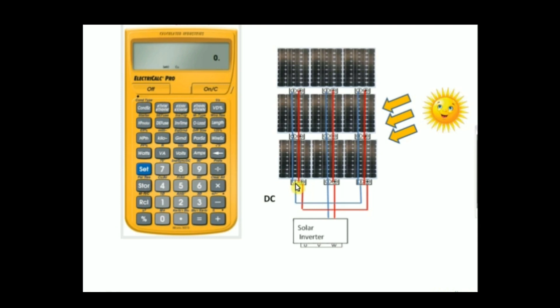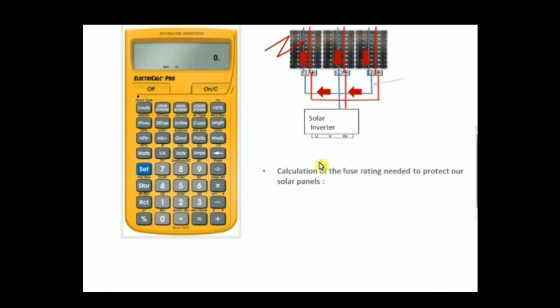Today we're going to see the calculation of the fuse rating needed to protect our solar panels. Here we have three parallel chains, and each chain delivers 8.26 amps. If we have a short circuit in one of these three chains, this will generate a return current in that chain, and the value of this current will be the sum of the other two parallel chains, so it's going to be 16.52 amps.